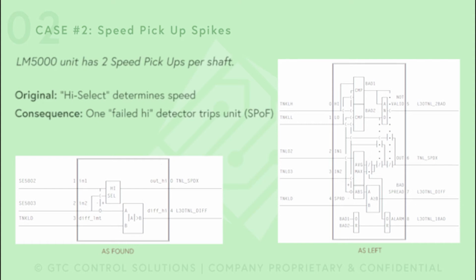So when I saw this, I said, well, there is another block, a not very well-known block, that has the I/O check, input-output check. And the input-output block selects the input that is working okay. So if one is out of the limits, high and low limits, it says this one is not okay and gives an alarm saying that one failed. Then it also calculates the differential between the two and also detects if the second failed. So if both failed, you're out of luck.